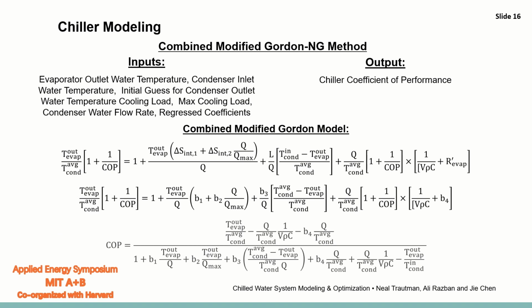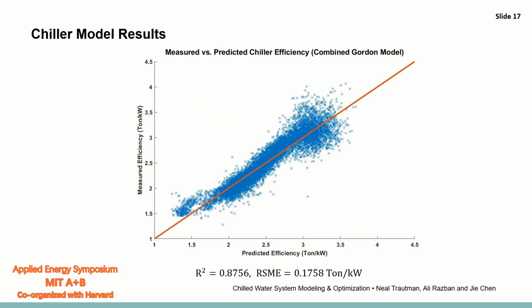So here you can see the combined modified Gordon algorithm that we created uses a variety of inputs to determine the chiller coefficient of performance, at which point you have to regress certain variables in the relationship, and then you can algebraically rearrange the equation seen in order to solve for coefficient of performance once you have regressed those variables. And here you can see the results of the algorithm that we generated. The R squared was found to be 0.8756 with a root mean square error of 0.1758 tons per kilowatt.